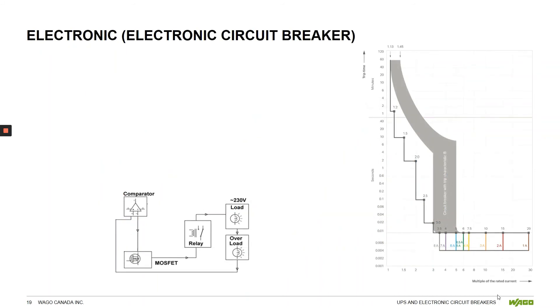One thing worth mentioning is that this series of breaker does not have an adjustable trip curve like other options, and the curve will be most similar to B characteristic. This breaker is ideal for control signals with small inrush currents as the trip time is very low.